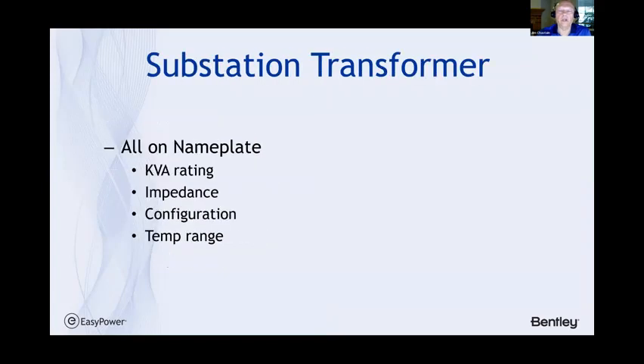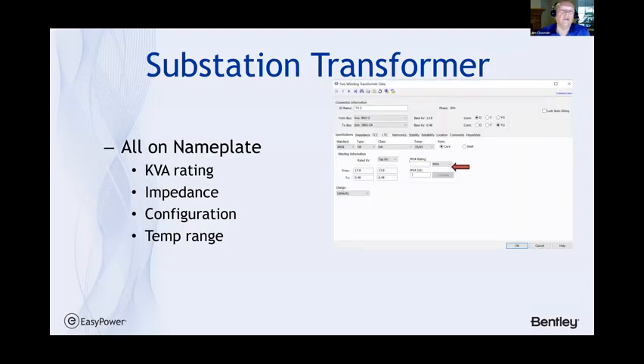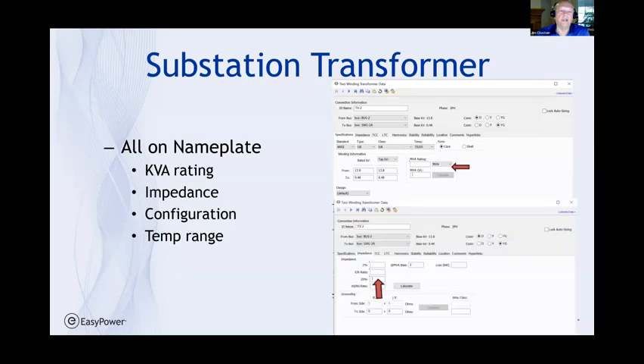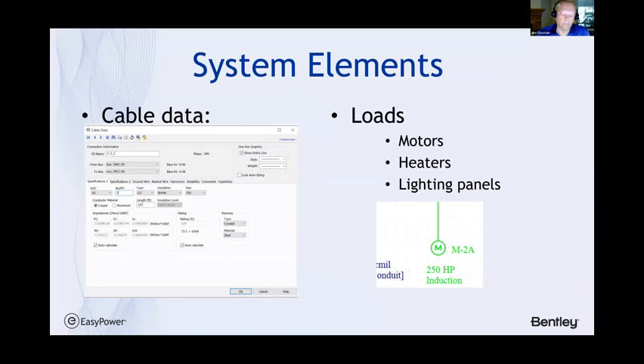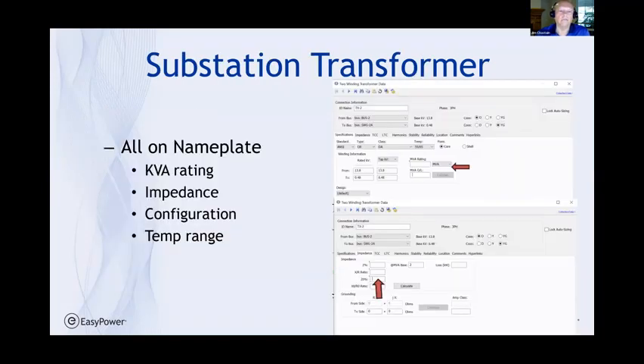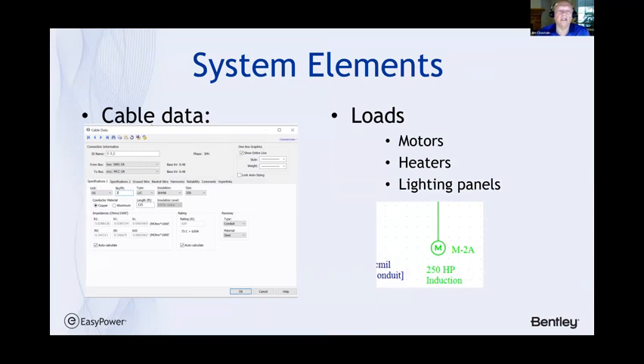And beyond that, the next most important element in the data collection for the one-line diagram is the substation transformer. And for that, virtually every bit of information is on the nameplate of the transformer itself. So this includes the kVA or MVA rating, the impedance, the configuration, whether this is delta-Y or delta-delta or Y-delta, and then the temperature range. Cable data is surprisingly important because it's going to influence the amount of inductive kick when an arc forms, and at the same time it limits the current based upon the length and the resistance of the cable. And then obviously motors, heaters, and lighting panels, which are the system elements and can be included in the one-line.